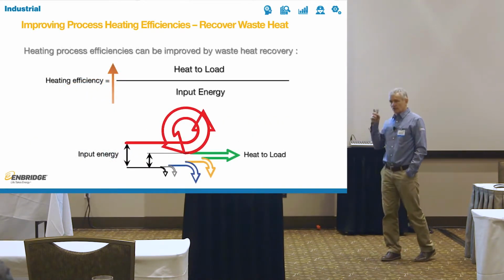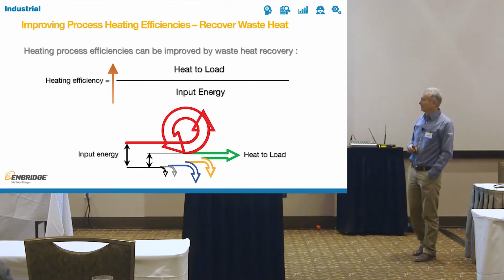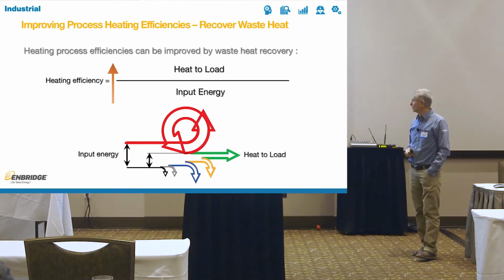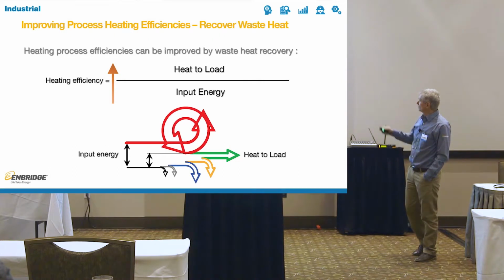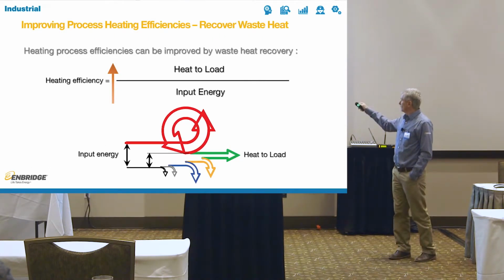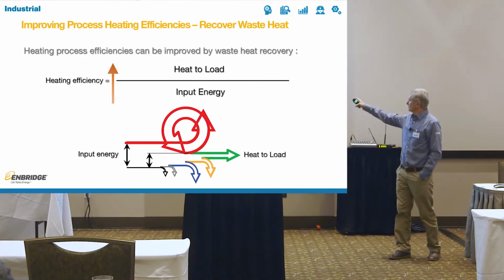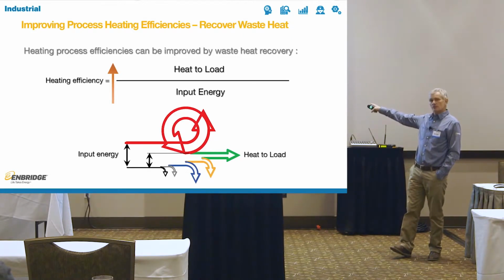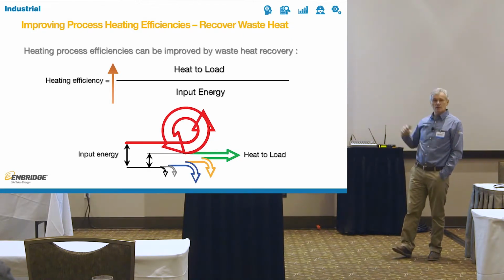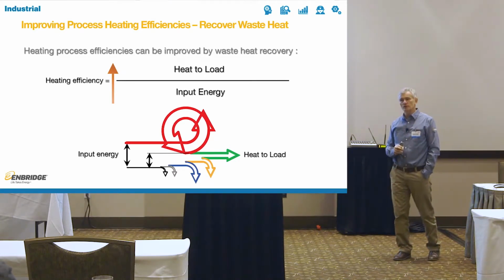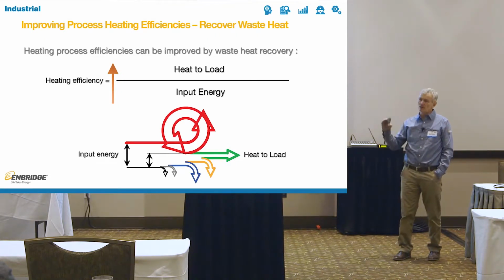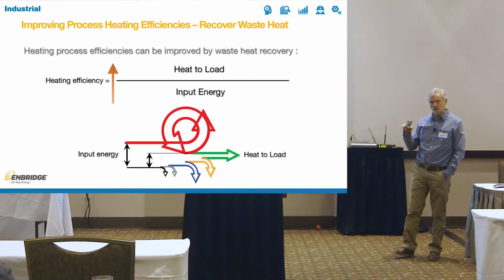Going back to our formula about heating efficiency, heat to load divided by the input energy: if you think of the Sankey diagram, and you can recover some of that loss and put it back into the system, you will increase your heating efficiency, just like you did by reducing that loss in the first place. So step one, can you reduce the losses? If yes, reduce them. If you cannot reduce them, recover the waste heat that those losses generate.